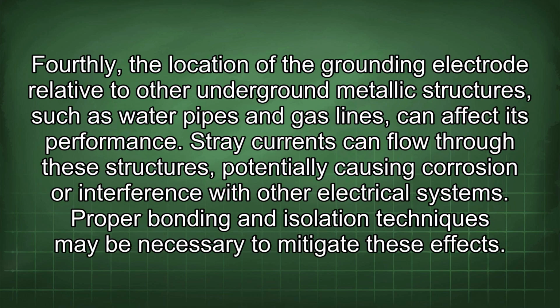Fourthly, the location of the grounding electrode relative to other underground metallic structures, such as water pipes and gas lines, can affect its performance. Stray currents can flow through these structures, potentially causing corrosion or interference with other electrical systems. Proper bonding and isolation techniques may be necessary to mitigate these effects.